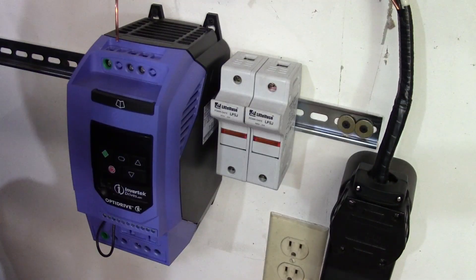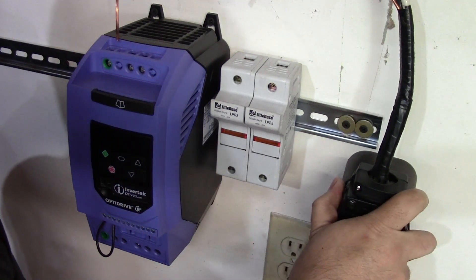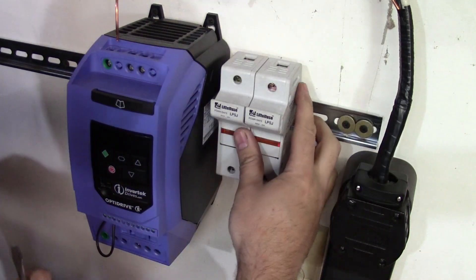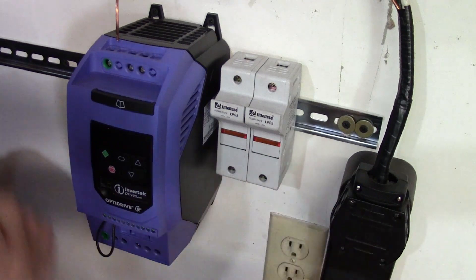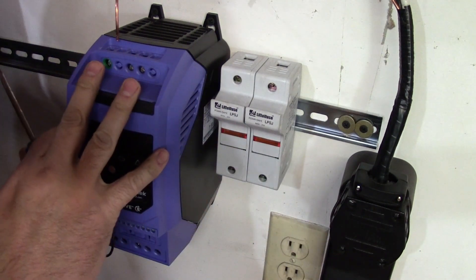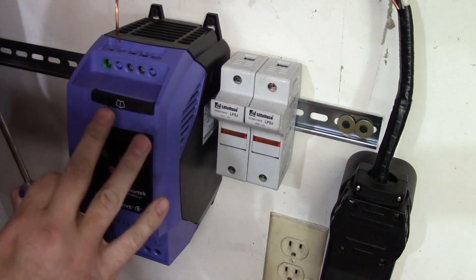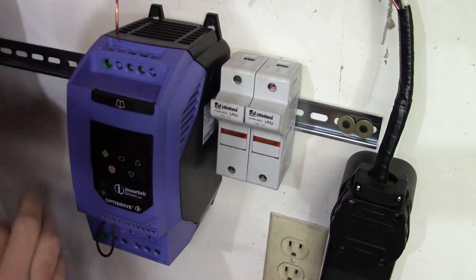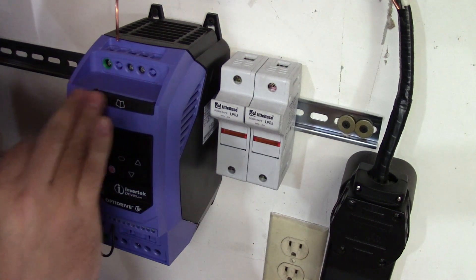Let's jump into the video. The first step in hooking up your Invertek VFD is to make sure the power is off. Most of the time you wouldn't even have this plugged in. I've confirmed that the power is off and the plug is wired correctly. It's important to run fuses when you're running a VFD so that way, if you overload the drive, you don't damage the drive. It's just a simple bit of insurance to protect your investment.